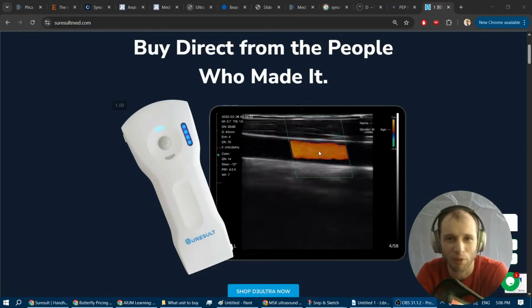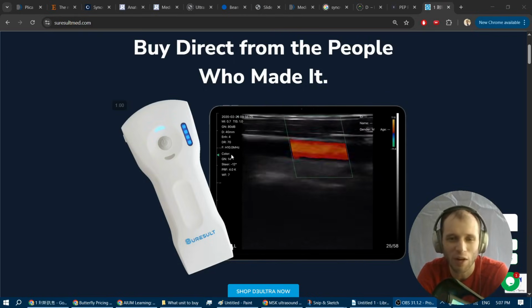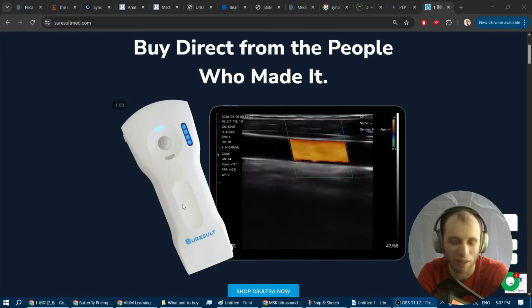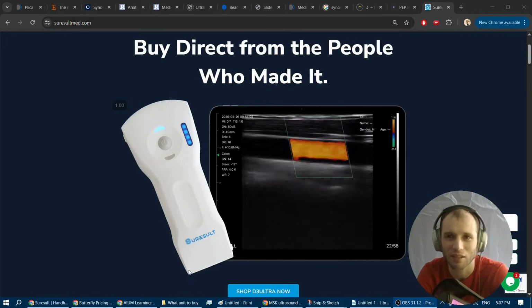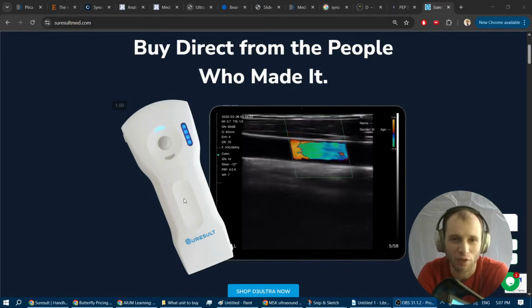So in this example here, if we look carefully, it says frequency 10 megahertz, right? And this is the maximum for the linear side, which is 4 centimeters across. As I mentioned, max 10 megahertz, and that's a little low for some things. But I find myself grabbing this over my Clarius unless I need something like 15 megahertz worth of detail, or unless I need 5 centimeters thickness of the image. It's just so much faster.